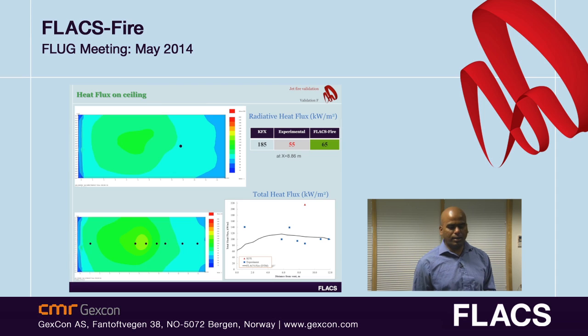The heat flux on the ceiling is shown here. In the SINTEF experiment, they have measured the heat flux at different locations. So we have compared FLACS-Fire prediction against those experimental measurements. The agreement between these two is generally very nice.